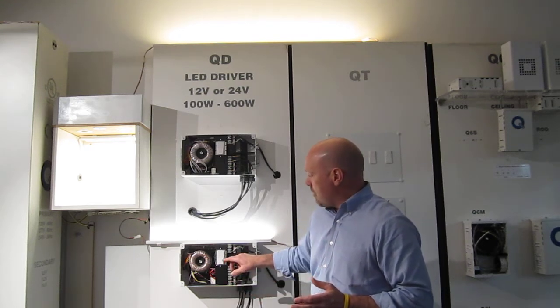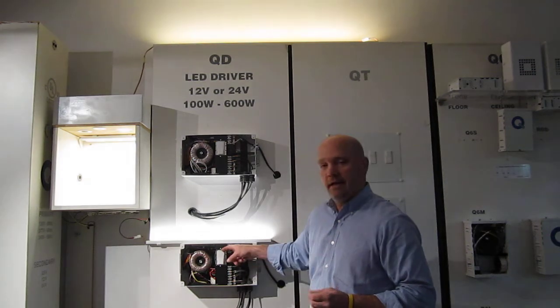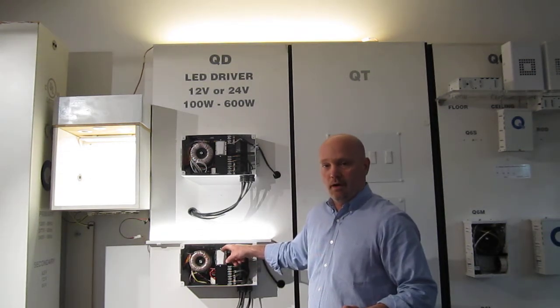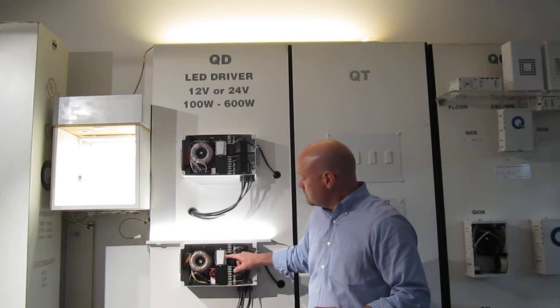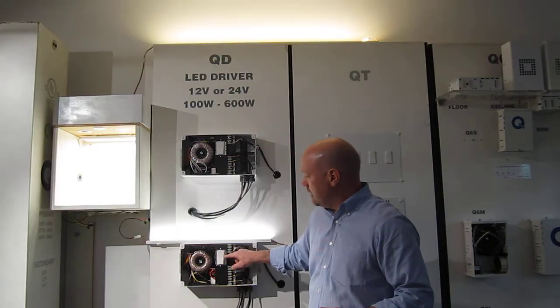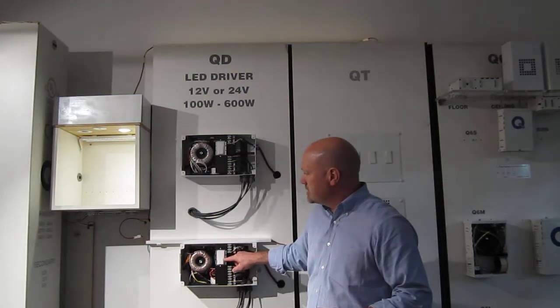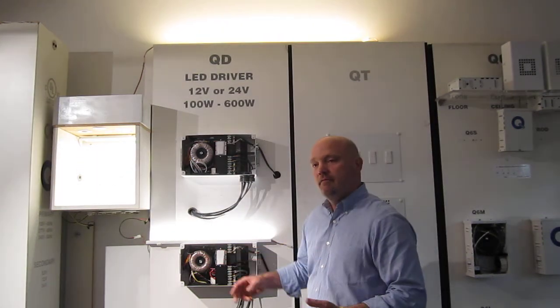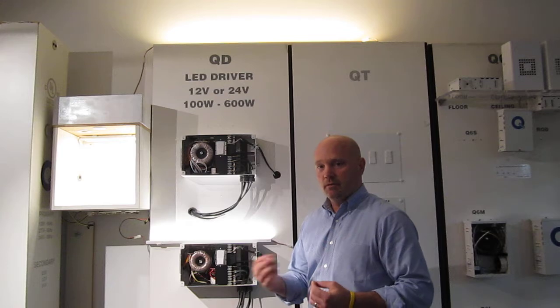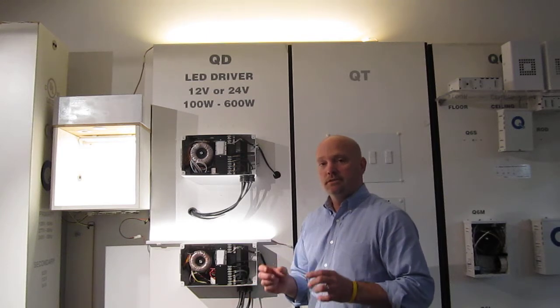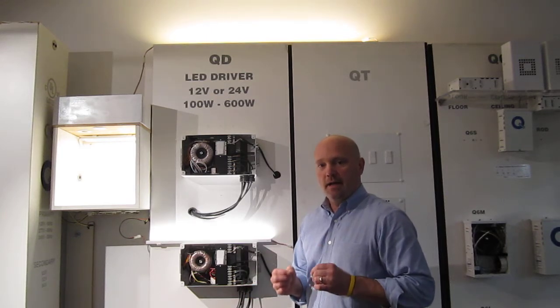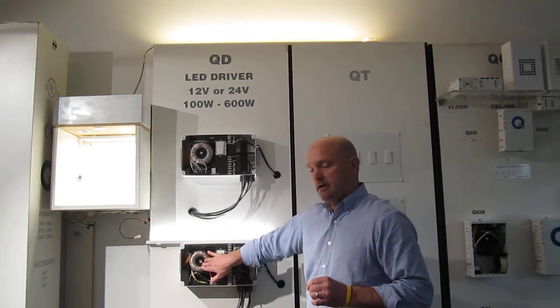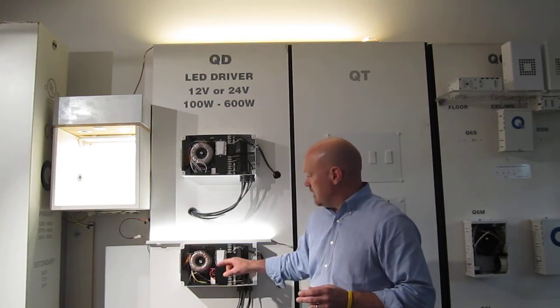One of the beauties of our product is with a typical magnetic low voltage dimmer, probably $40 at your local wholesale house, you can control these LEDs not only on and off, but you can dim the lights up and down. So it's a very simple control if you need that. If you need to tie it into a system, be it a Qtran system or whoever, as long as that module is rated for magnetic low voltage, which is an inductive load, you can dim these lights up and down.